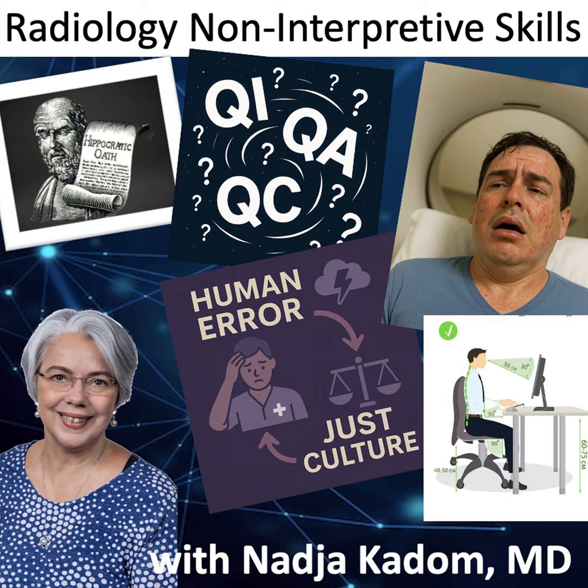If you're quenching a magnet, it has to be for a life or limb threatening situation, right? If it's a really bad uncontrolled fire where you're going to have the fire department coming, go ahead and quench it. If somebody's pinned to the machine, go ahead and quench it. If somebody's having some sort of issue where they can't move in the machine and it's because of an object, go ahead and quench it. So anything life or limb, I wouldn't hesitate to quench. Other things like things getting pinned to the machine, we can ramp it down through the field service engineers.